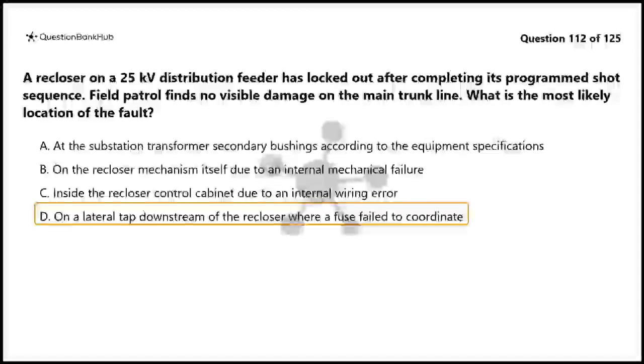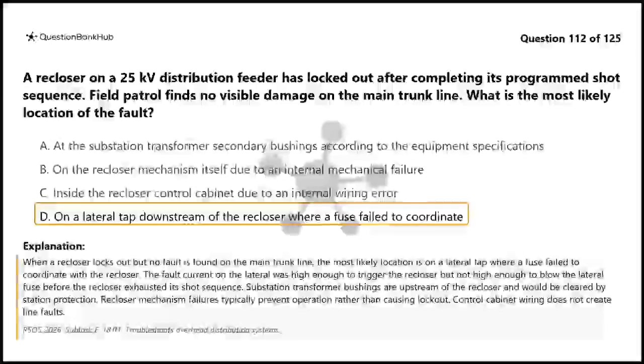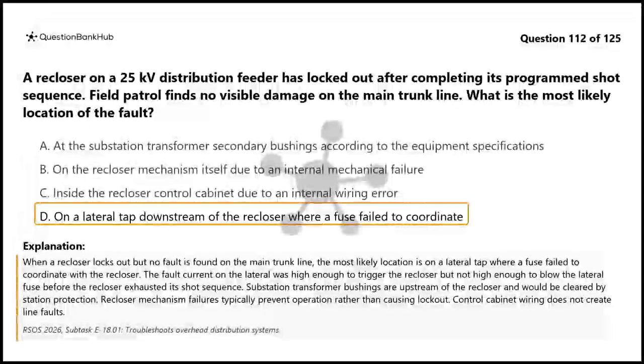The correct answer is D. When a recloser locks out but no fault is found on the main trunk line, the most likely location is on a lateral tap where a fuse failed to coordinate with the recloser. The fault current on the lateral was high enough to trigger the recloser but not high enough to blow the lateral fuse before the recloser exhausted its shot sequence.